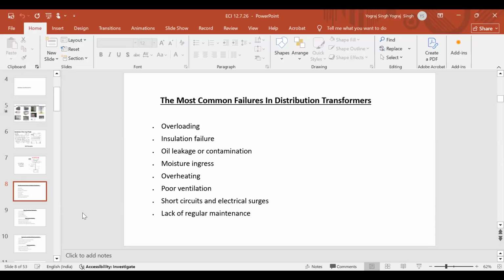But loading is pertaining to each phase. If, for example, a transformer is 600 kVA, each phase will see 200, 200, 200 kVA each. Now, if one of the phases is loaded to 250 kVA, another one is loaded to 150 kVA, and the third one is loaded to 200 kVA, it is not balanced, meaning one phase is overloaded. So some cushion is always provided by the manufacturer. It will take that much of load.